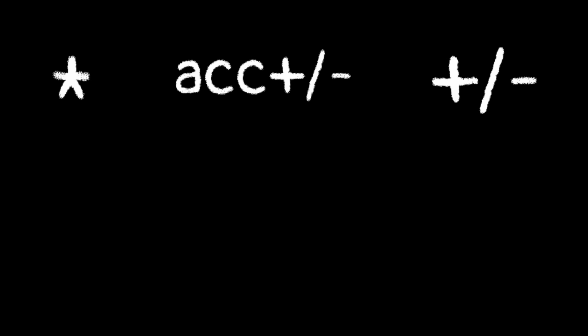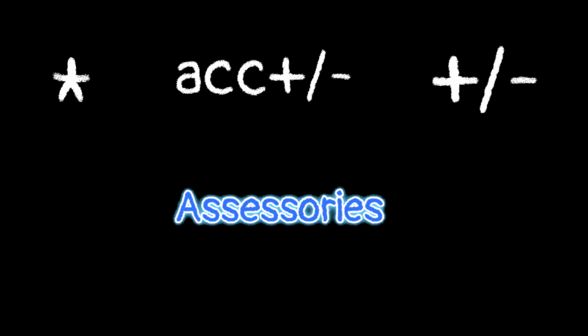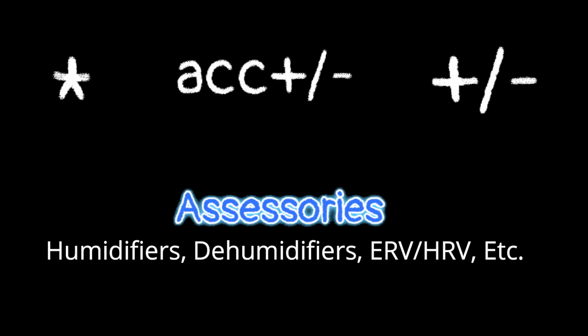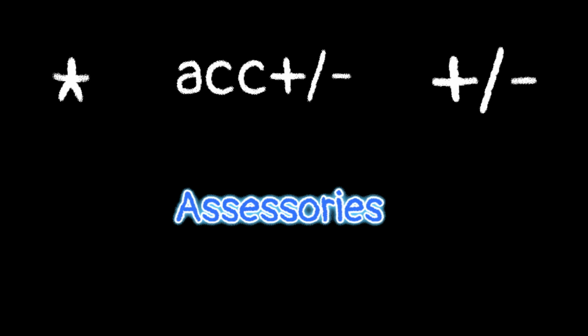Most of the other terminals on thermostats are for accessory items. These are for accessories like humidifiers, dehumidifiers, energy recovery or heat recovery, ventilation systems, and so forth. Terminals labeled L, F, A, sometimes LA, are typically just alarms, notification of some kind, just an alert to let you know something's wrong. You'll also see terminals like U1, U2, S1, S2. These are typically temperature sensors. A lot of systems might take an outdoor temperature and an indoor temperature to run their programming cycles.